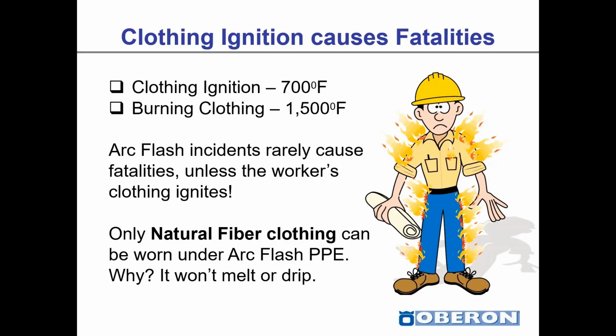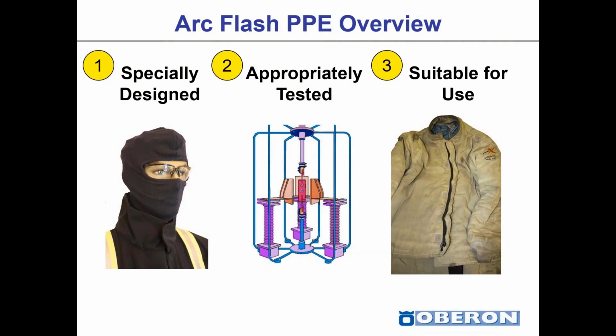It's important to note that only natural fiber clothing can be worn under Arc Flash PPE. The reason for this is that it won't melt or drip. Natural fiber clothing will certainly burn, but the melting and dripping is where we increase the depth of injury in terms of the burns, and it increases the severity of the injury caused to the worker. In review, for Arc Flash PPE we have 3 different points. Again, specially designed, appropriately tested, and suitable for use. Those are the 3 key points you want to consider when you're reviewing Arc Flash PPE.